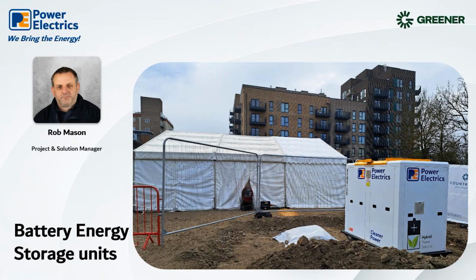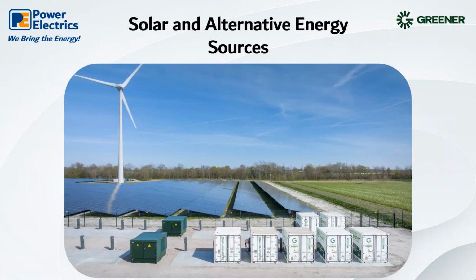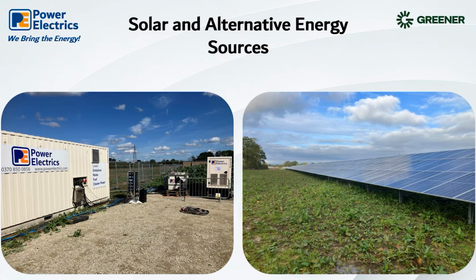It's also really important, if you start using grid supplies, to understand how these interact together. So grid generators and alternative energy sources such as solar and wind can all be used really well, but you also need to make sure you're understanding the regulatory considerations, such as G99 protection alongside the grid and G100 for the import-export regulations. Just because it's there doesn't mean you can do it straight away.